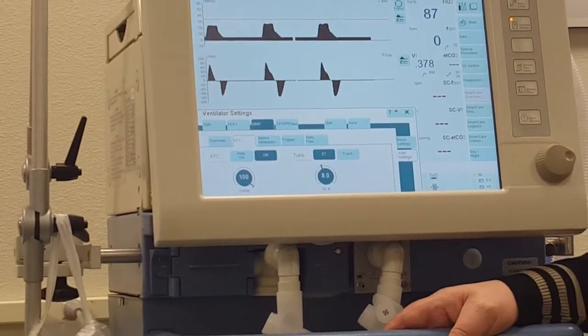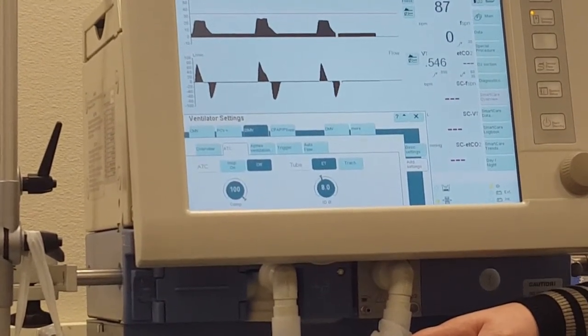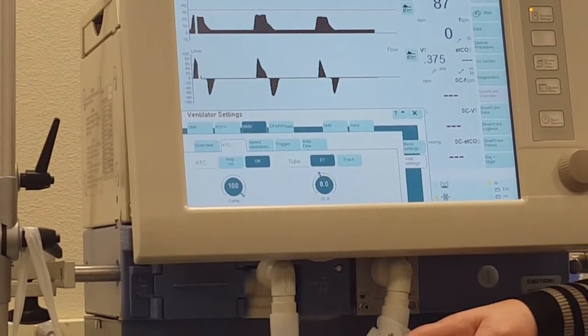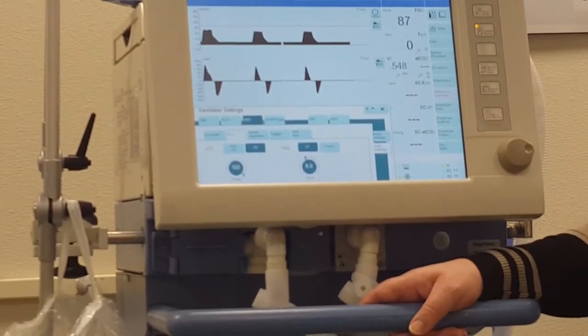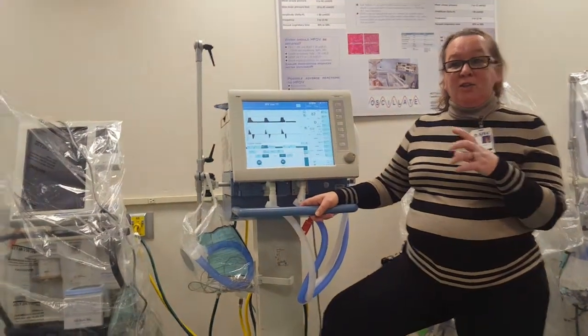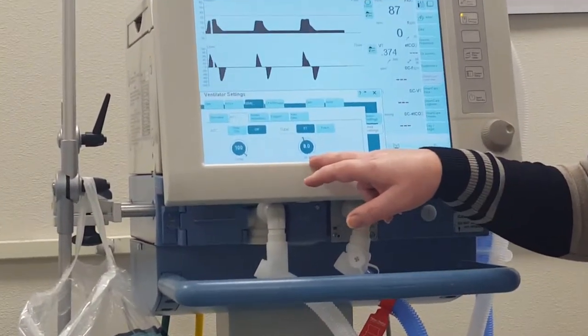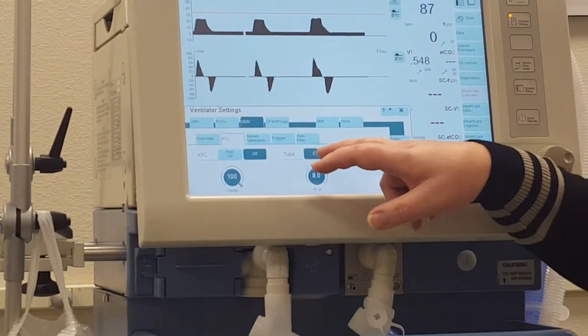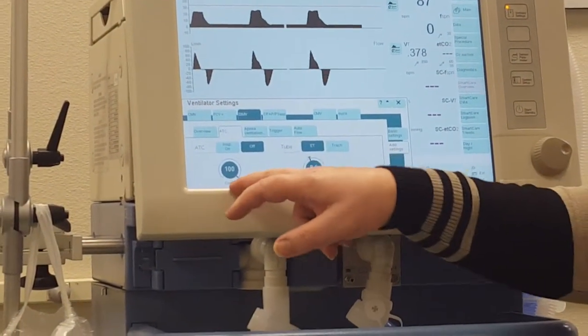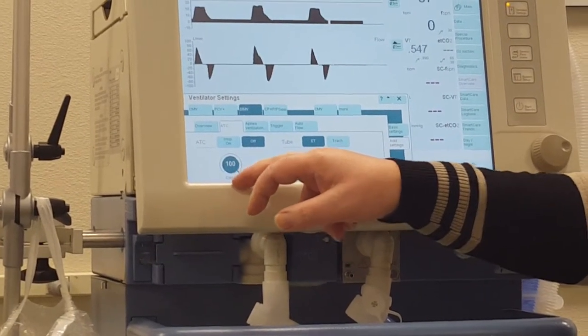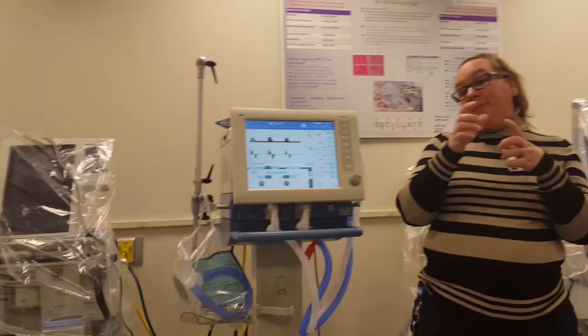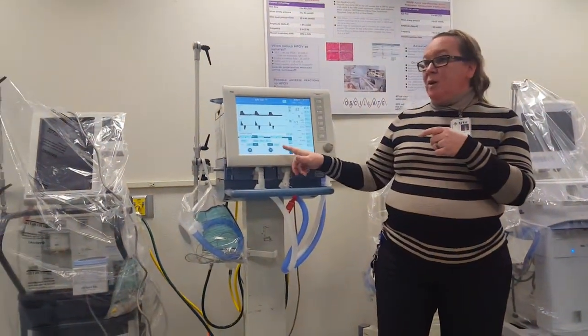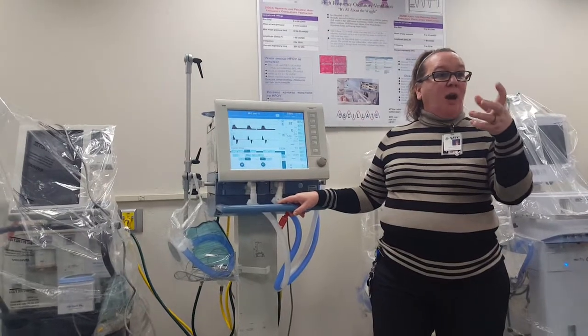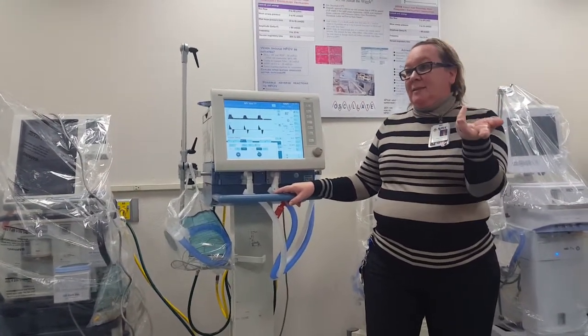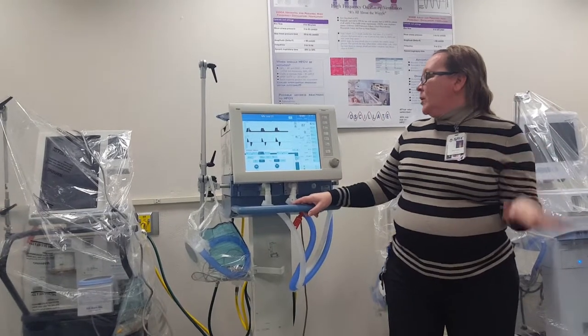It's really a setting we're going to talk about more when we go into weaning, but I tell you just so you know what it is. Automatic tube compensation has nothing to do with the circuit. It's a setting that compensates for the size of the ET tube or the trach that your patient has in. So you'll see this gives me a section where I can set ET tube size or trach size, and then how much I want to compensate for it. So this helps overcome the resistance a patient has to do by breathing through a tube. So automatic tube compensation puts an amount of pressure in there to automatically help my patient compensate for the ET tube that they have in. So that's what that is. And we'll talk about it more later on.